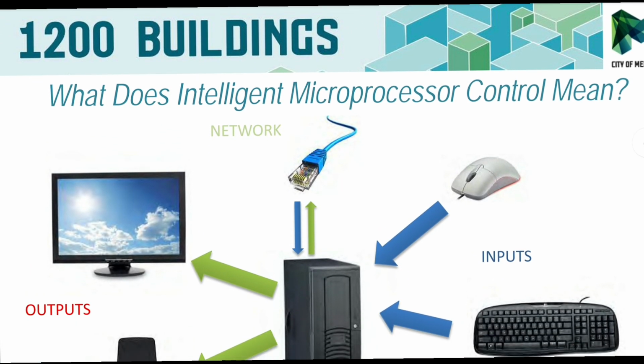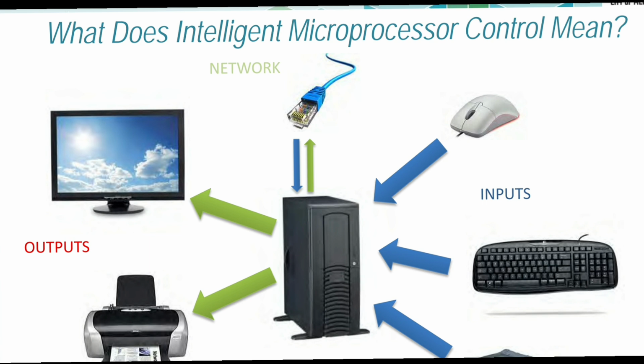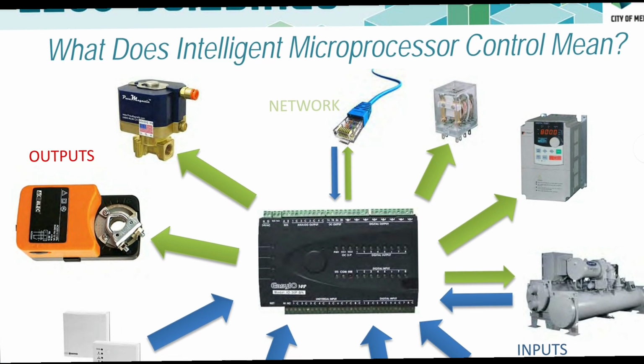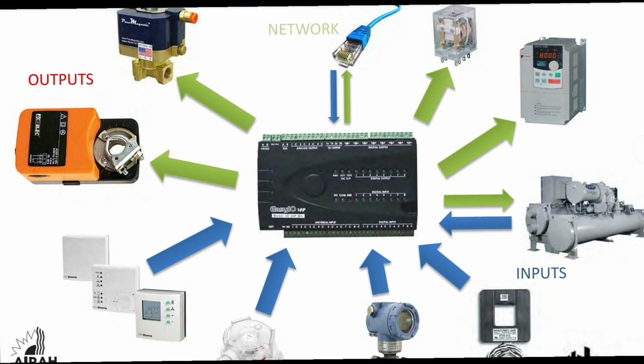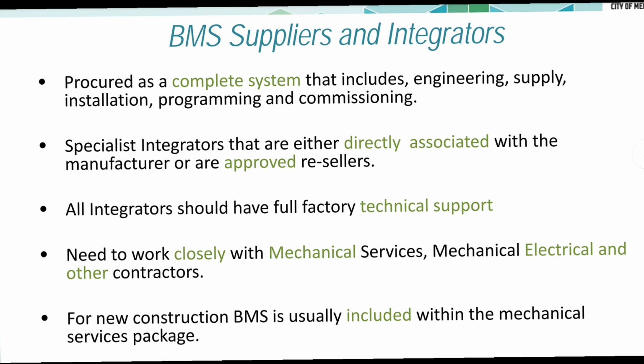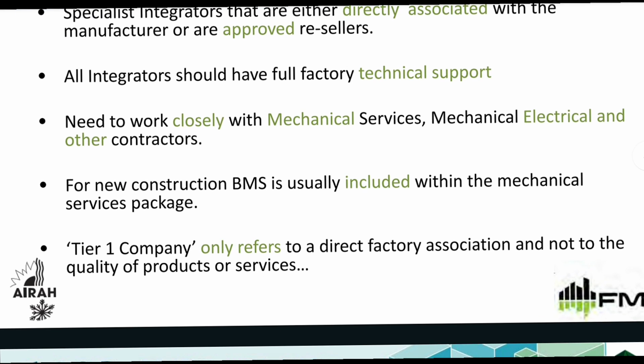How does integrated microprocessor control work? This is the network, outputs, CPU, which you already know. These are called DDC panels. All devices like chillers, control valves and temperature meters are connected to DDC panels. BMS supply and integration: supplied as a complete system that includes the engineering, supply, installation, programming and commissioning. Specialist integrators are either directly associated with the manufacturer or are approved resellers. All integrators should have full factory technical support and need to work closely with the mechanical, electrical and other contractors.